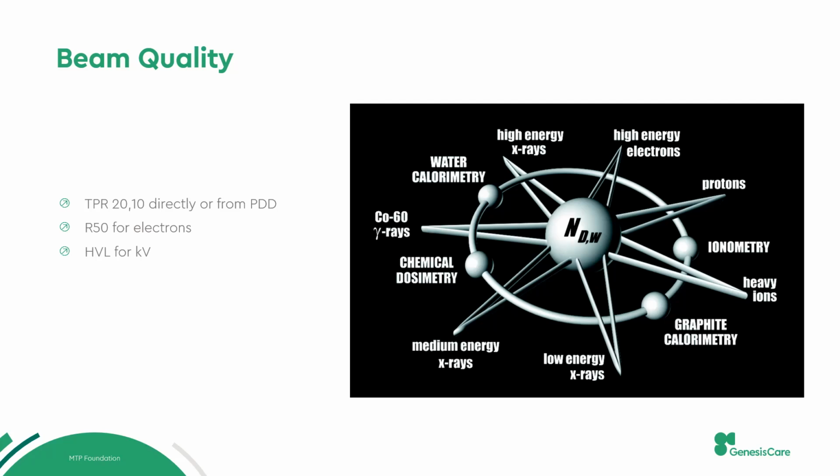Okay. But TRS 398 gives you a different formalism, if you don't want to go into changing the SSD, because for this you have to put your 90 and that 80, and that needs time. An empirical formalism is there in TRS 398. You can directly convert from PDD to TPR, which we are doing here. So that's the simple way of doing it as well.